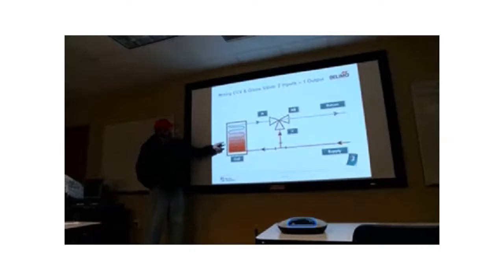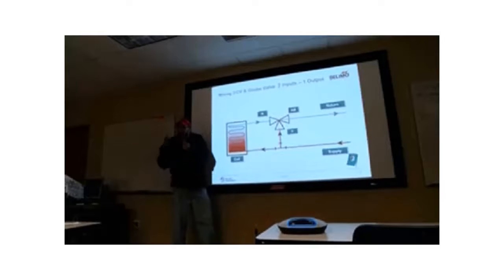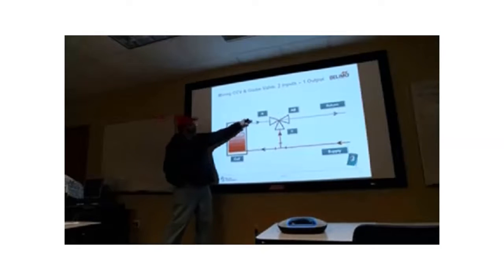I want to show you something here, and I'll emphasize it when we go to the catalog. But in both of these cases, the A port is always closest to the coil that it controls. Remember that, write it in stone, write it on your forehead, whatever you want to do. But this is important because you can find valves that were installed wrong. For instance, someone might say, hey, I don't have enough room to put it in that way. So what I'm going to do is I'm going to put the B port there. It doesn't work. It doesn't work well. Let's put it that way. So if you remember that the A port should always be connected closest to the coil, I don't think you'll ever get it wrong for both a characterized control valve and a globe valve.